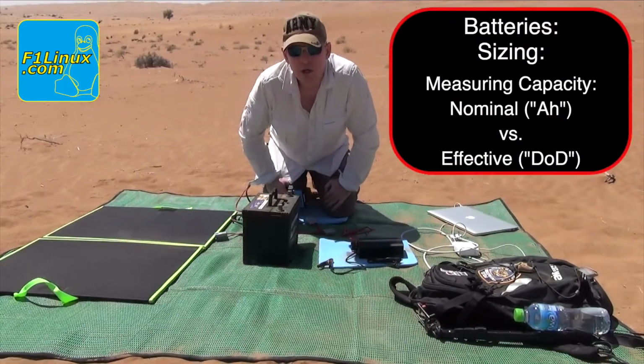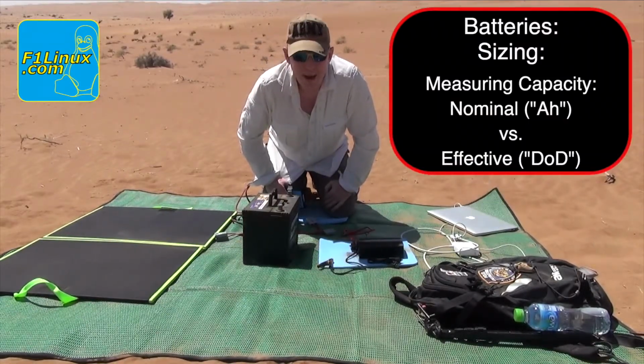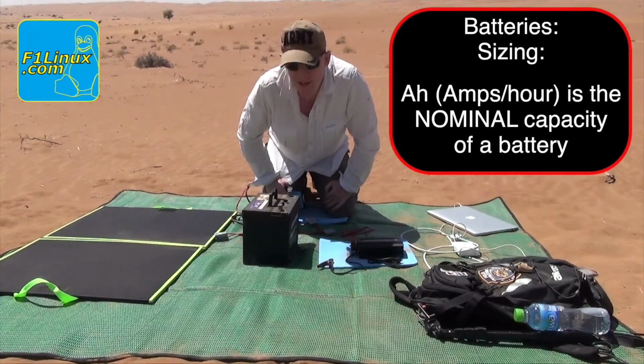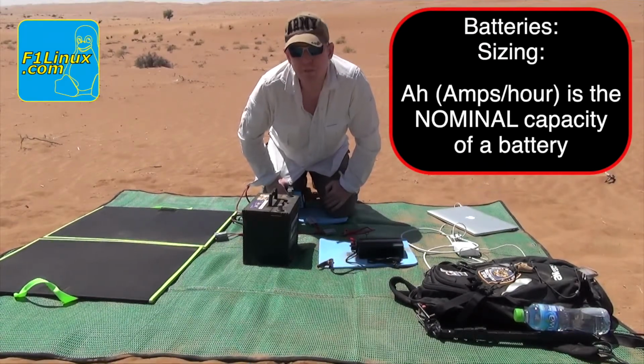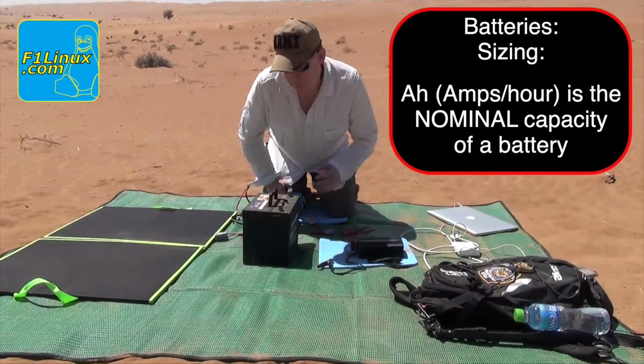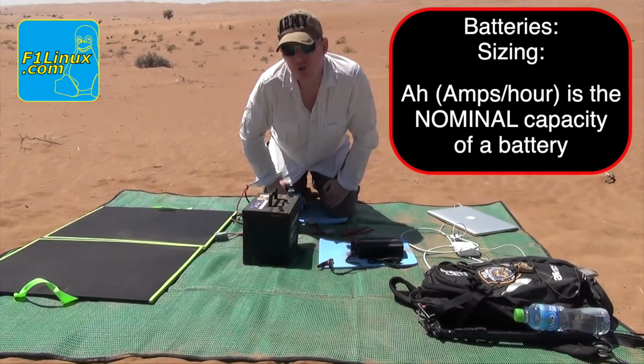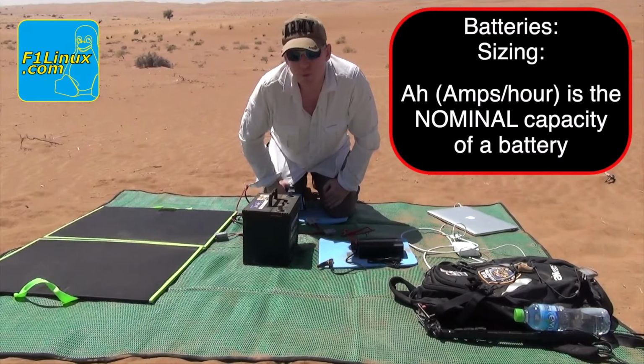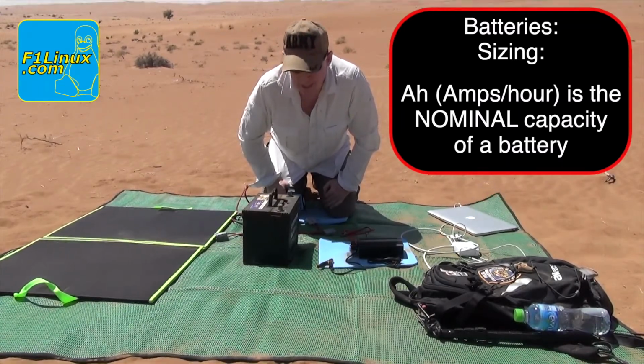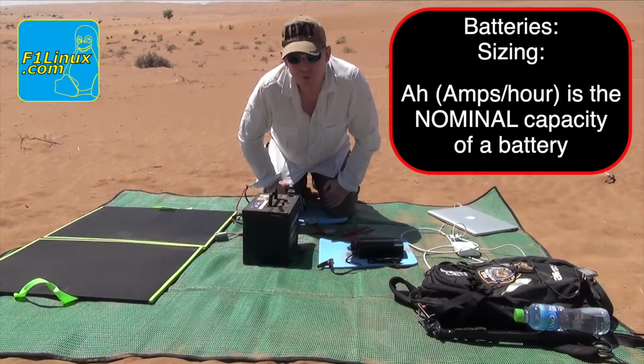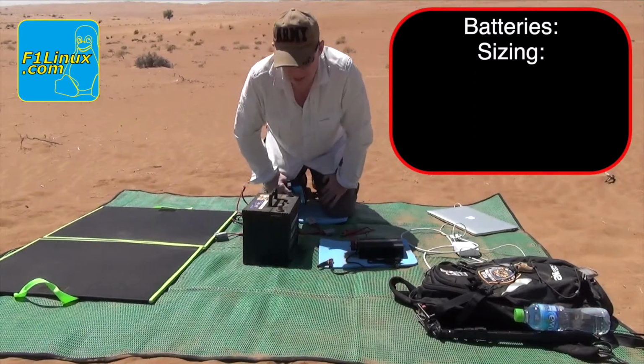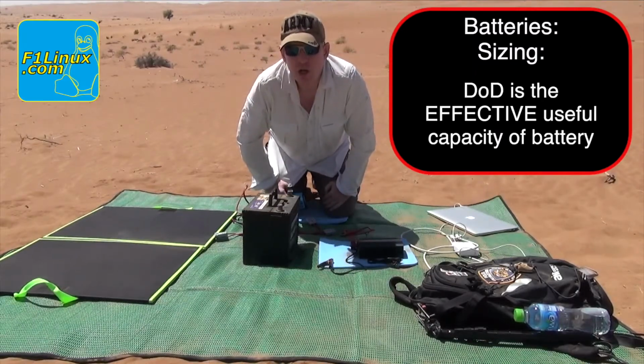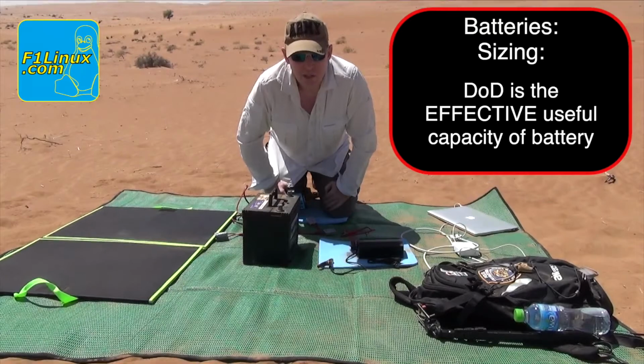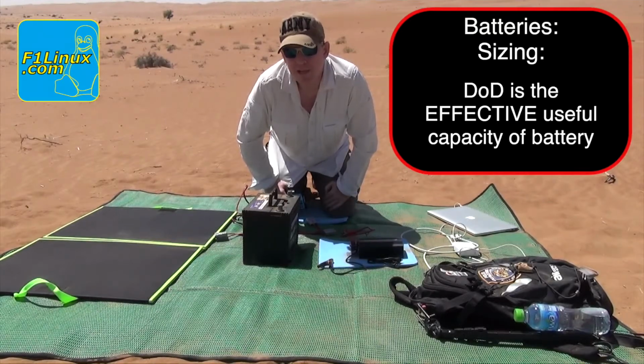Batteries are rated in AH, ampere hours. That is to say, a 1 amp device could be powered for 100 hours, theoretically, with a 100 AH battery. Now, that's only half the story. That's a theoretical number. There's something called depth of discharge. That is the practical limit to which you can drain the battery.